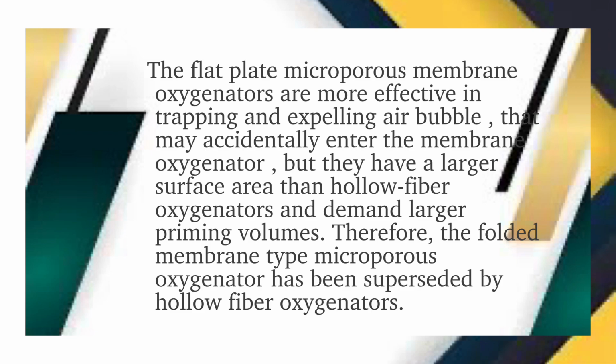The flat sheet microporous membrane oxygenators are more effective in trapping and expelling air bubbles. Bubbles may still enter the membrane oxygenator, but they have a larger surface area than the hollow fiber oxygenator and demand a larger priming volume. Therefore, the folded membrane type microporous oxygenator has been superseded by hollow fiber oxygenators.